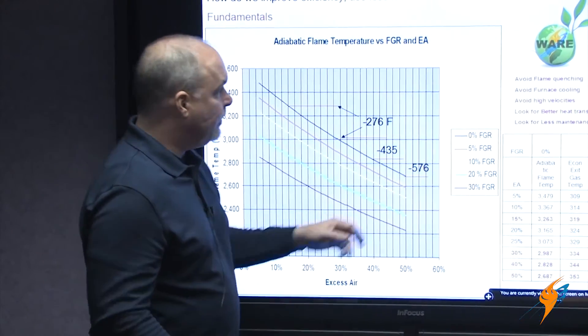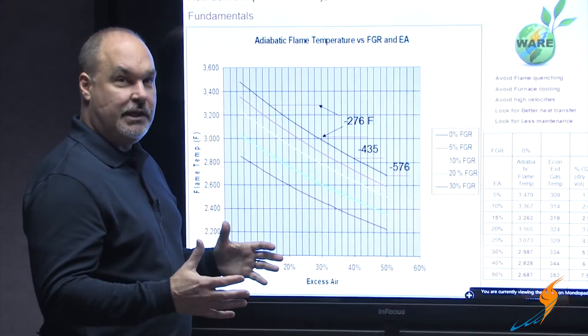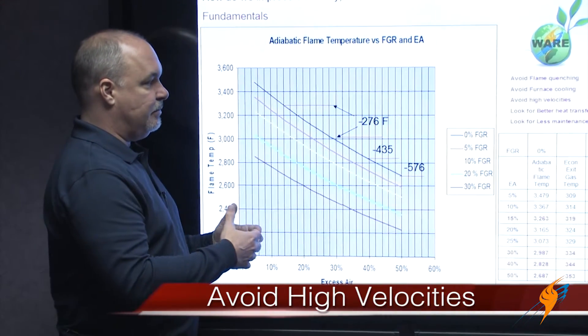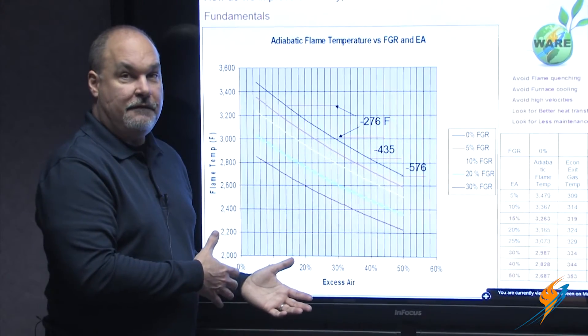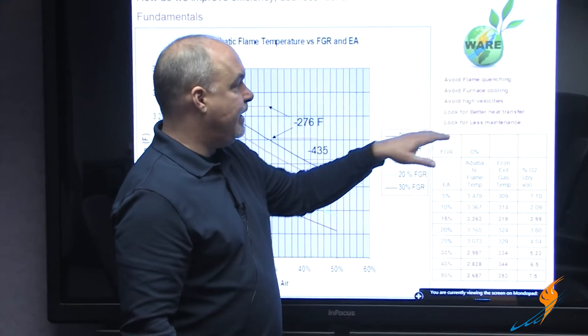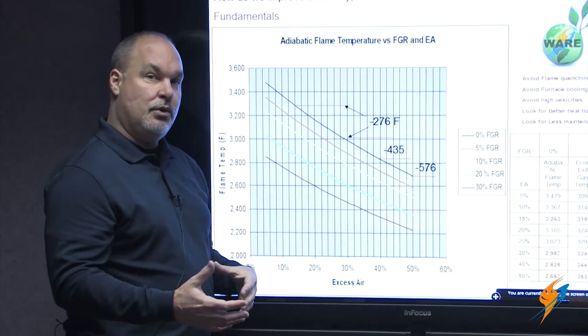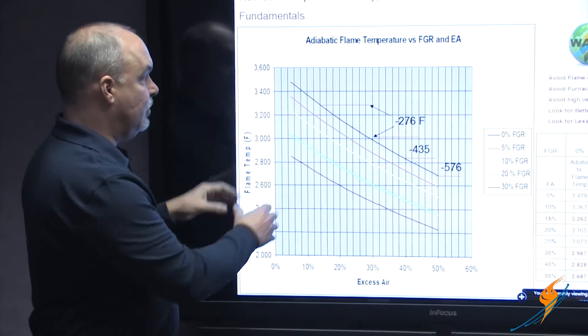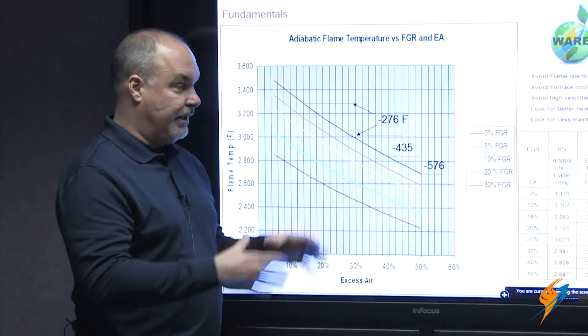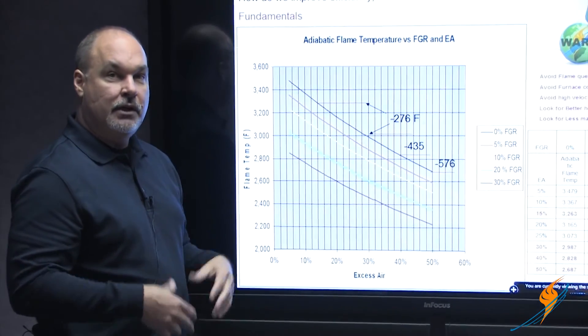Not all low-NOx burners are the same. We also want to avoid furnace cooling — if we lower our temperatures and increase the air, we've got our heat exchanger battling against us. We want to avoid high velocities as well. Traditional systems can use lower horsepower fans, but the velocities running through there quickly mean the heat exchanger can't perform exactly like we'd like. By avoiding some of these things, we're looking for better heat transfer and less maintenance — there's equipment out there with fewer moving parts. These are the fundamentals that the average person simply doesn't see when they look through the peephole and say, 'I've got a flame — why is yours any different?' These characteristics are really what cause that difference.